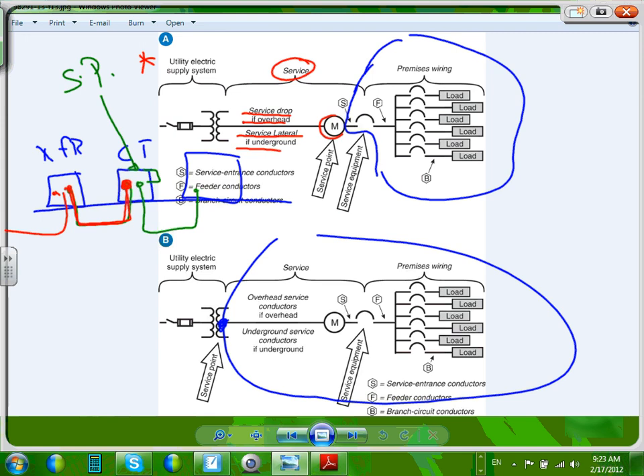So let me tell you what you own. Anything that's red, the utility owns and operates. They own the transformer and the feeder to it. They own and operate the cable to the CT cabinet. They might ask you to put in a conduit for them. You own and operate everything else. The CT cabinet, well, you own it, and you bring your cable to the building. That will be very similar to the first one right here, where the CT cabinet is. This most likely will be the CT cabinet or a meter.